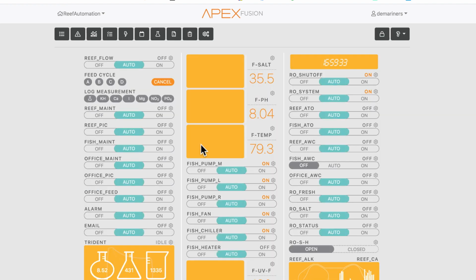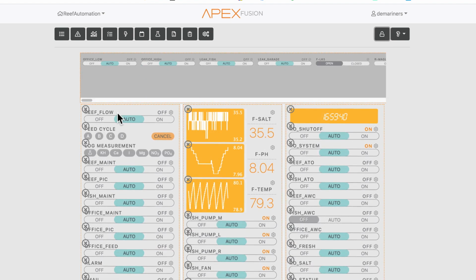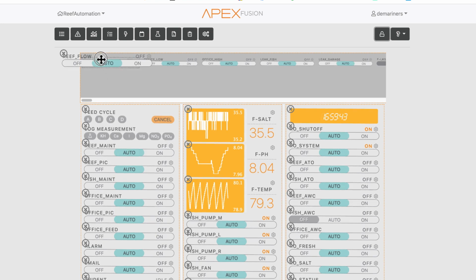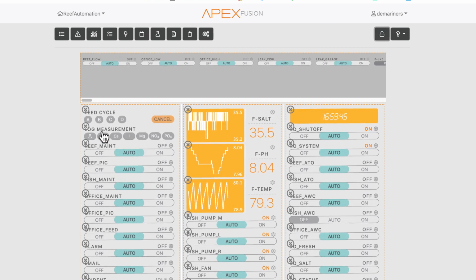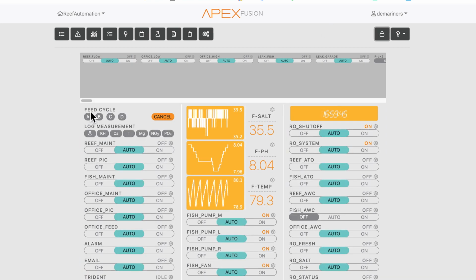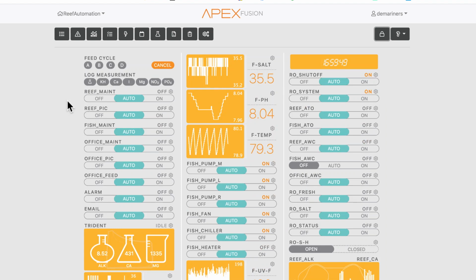So that's another way that you can program your flow so that you don't have to worry about getting alerts when you're in certain modes. You could also do that with a feed cycle. So you could say in that virtual outlet, if feed A is on, then turn off the flow virtual outlet, and therefore you wouldn't get an alert while you're feeding. So there's a number of ways that you can use the flow, and there's a number of ways you can use that number, like I said. But that's the basics of programming the flow sensors.